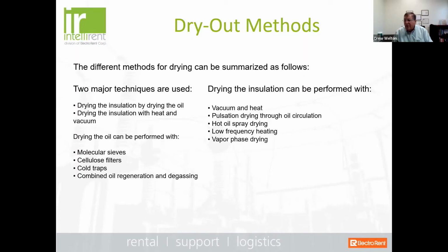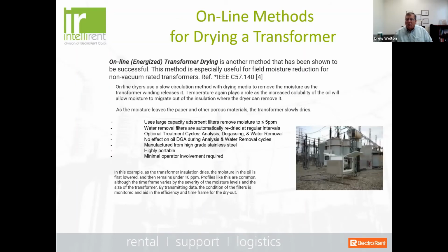So the other is that we can dry the oil again with cellulose filters, molecular sieves, cold traps, combined with oil regeneration and degassing, many different ways. But what we're doing is we're addressing the moisture that's in the oil. Well, one of the methods that we've found, and we found this to be quite effective, is an online drying method for transformers. So there are devices that you can get. They're high volume, high capacity filtration systems that can be done during the online process. In other words, you can have your transformer up and running during this drying out process of the oil.